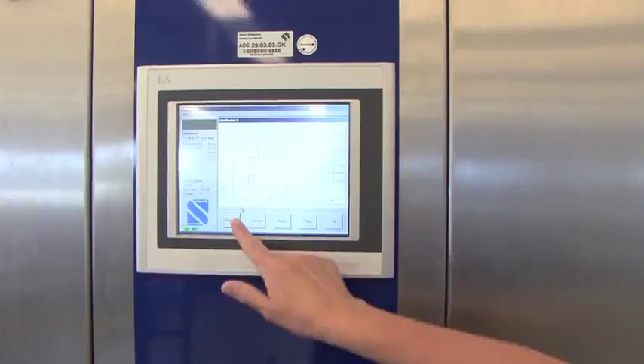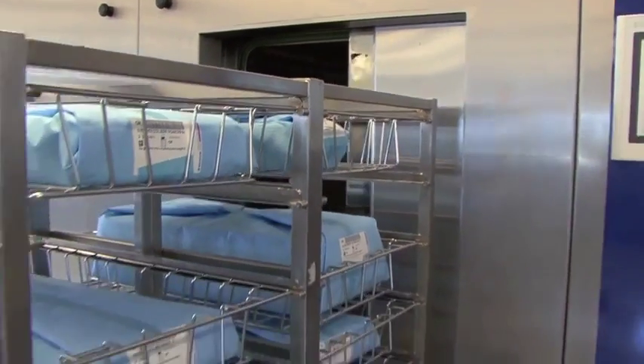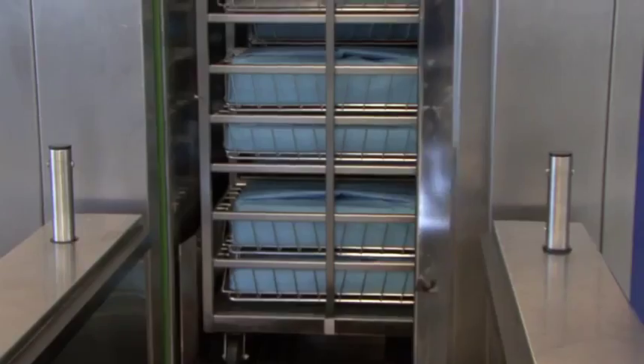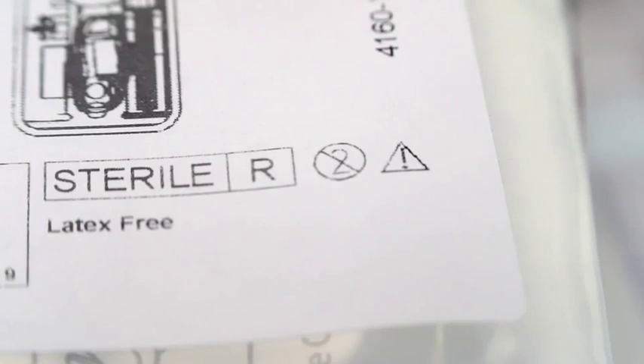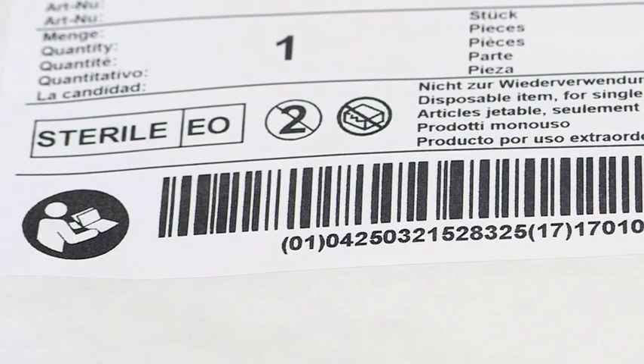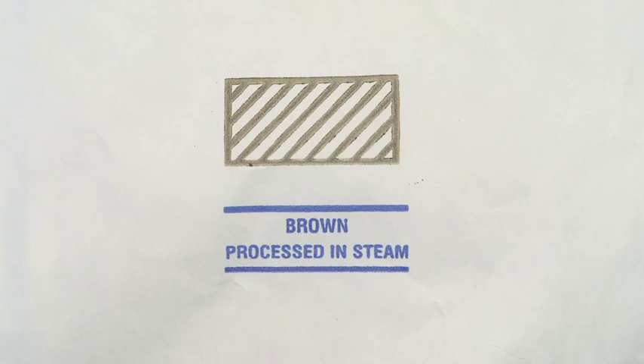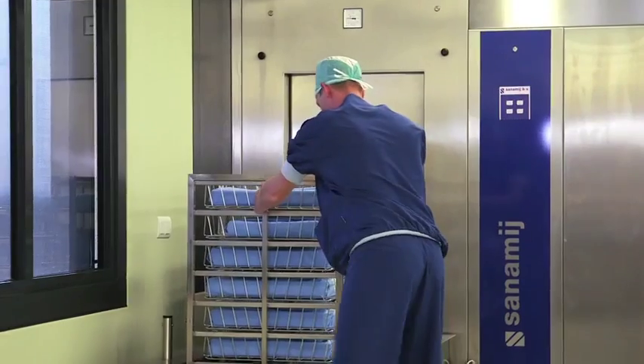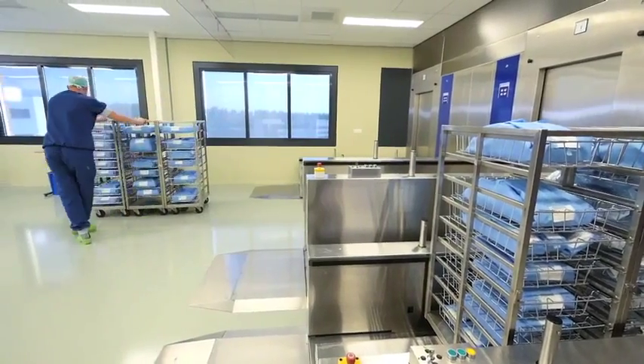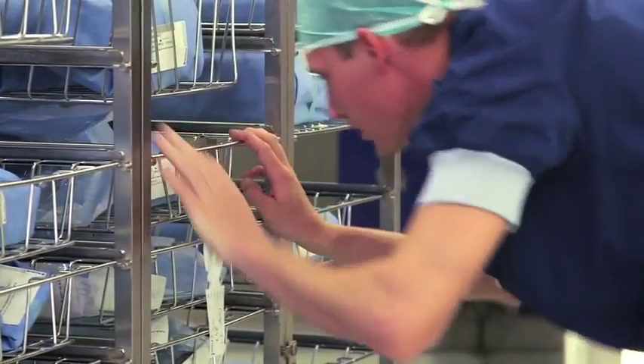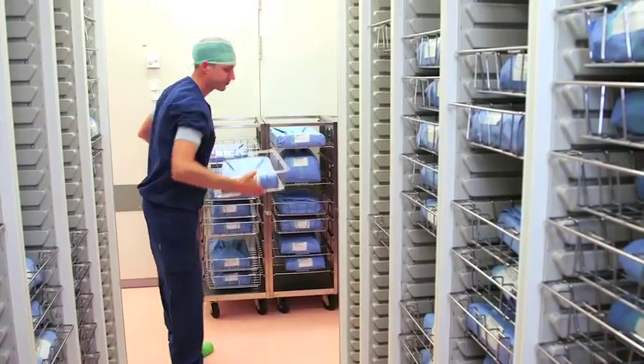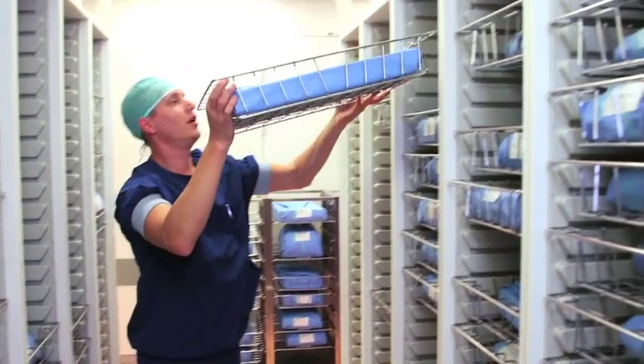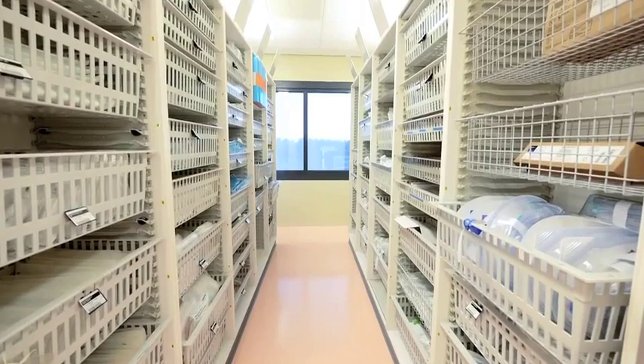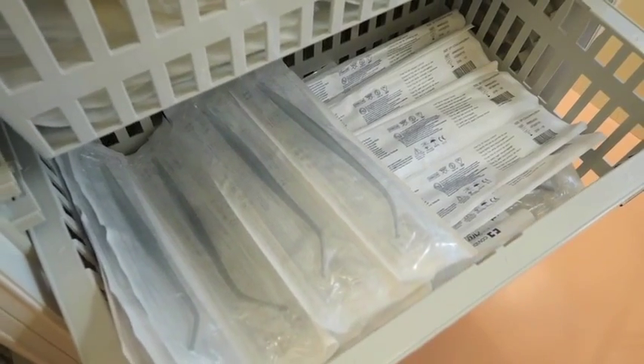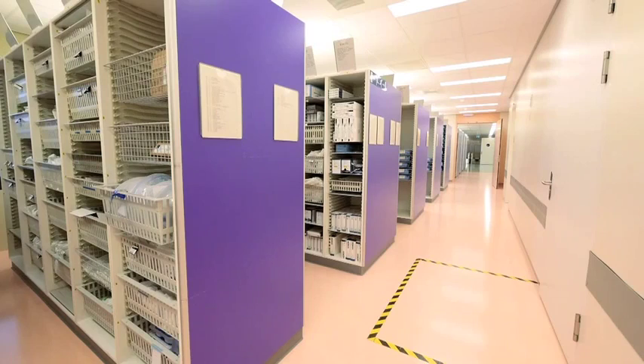All medical devices are sterilized in their sterile barrier system before they're used. There are a variety of sterilization methods used. These include irradiation, indicated on the label as R, ethylene oxide gas, indicated as EO, and steam. The chosen sterilization method must be compatible with both the device and the barrier system. A medical device, once sterilized, must remain sterile until it's used. Barrier systems are able to keep medical products sterile for years, provided they do not get damaged. The sterile device and its barrier system must be transported and stored according to recommended conditions.